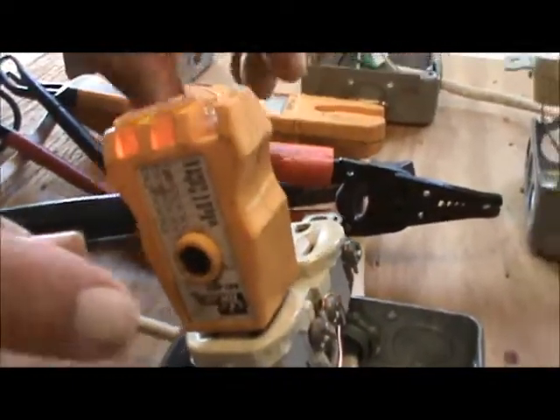One of my students is out working now in the electrical field, and he had an inspector who said the ground fault won't trip when I push the reset on my polarity tester. This is a polarity tester, and you'll see right here there's a button. If you push that button, it's supposed to trip — but it didn't trip.